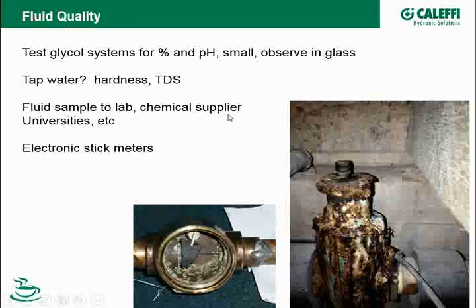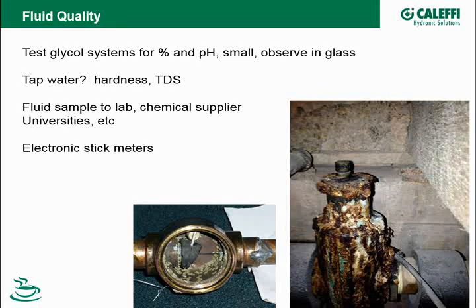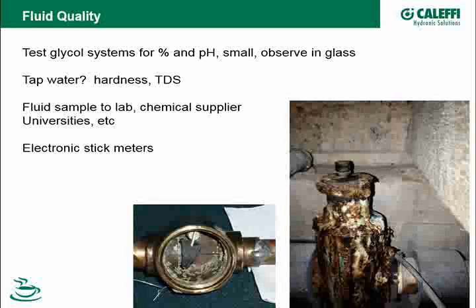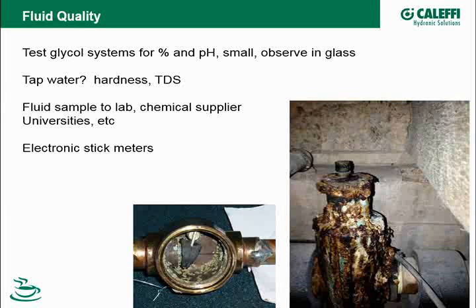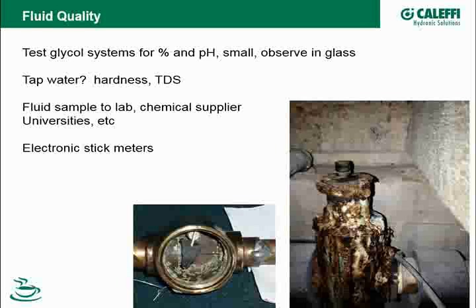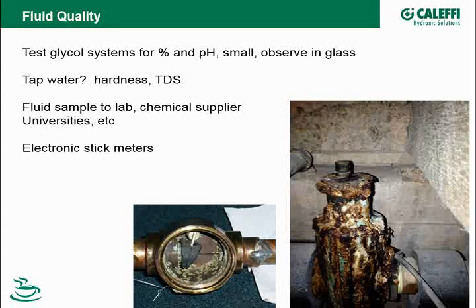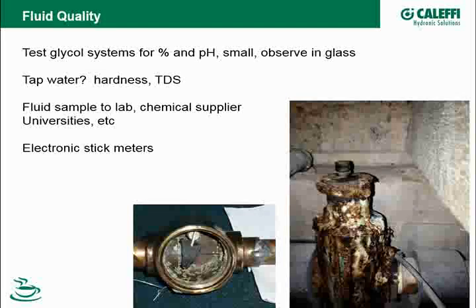Sometimes the chemical suppliers will do that for you. If you are filling your systems with inhibitors or with glycols, whatever manufacturer's on the label, if you buy that from a wholesaler, check with them. And lots of times they'll ask you to. Sometimes they'll even give you a little sample jar to take out to the job and put a sample in, and they can do a little bit more of an analysis than you would probably be able to do just on the job site. Universities, sometimes the local colleges will have a department that can do water analysis, especially fill water, if it's city water, something like that.